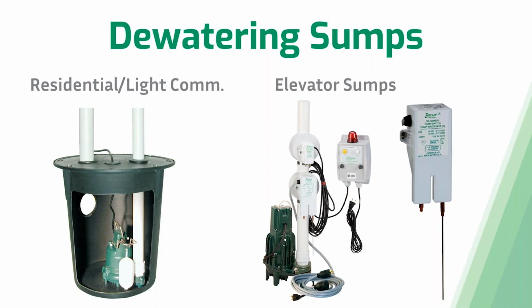The way that you do that is using an oil smart pump switch, and that can be seen here on the right. This oil smart pump switch will actually detect oil using this short probe here. And once it detects water, it will then turn the pump on and pump that water down into the bottom of that longer probe. The reason why this works is that oil floats on top of water. So this way you always know that the oil is staying in your system while your water is being removed.